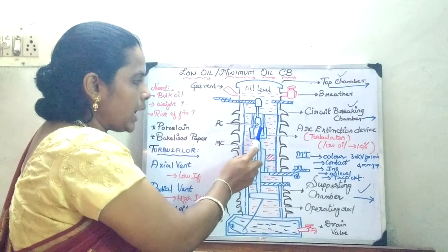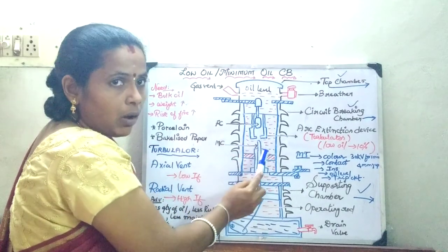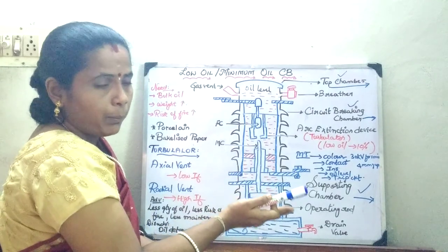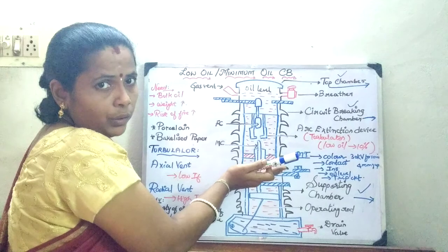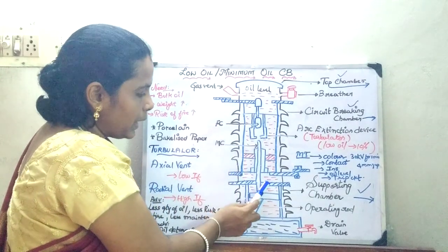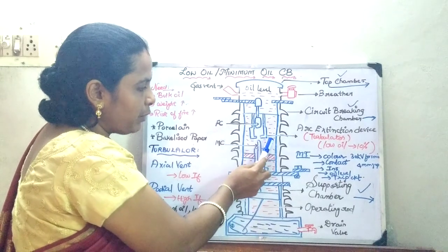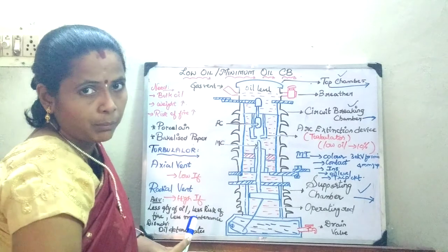Because whenever the arc is struck, the heat in the arc is going to decompose the oil and the carbon arc deposits are going to be in the oil itself. In that case here, this partition serves a better purpose because this partition does not allow the oil from the circuit breaking chamber to enter into the supporting chamber.